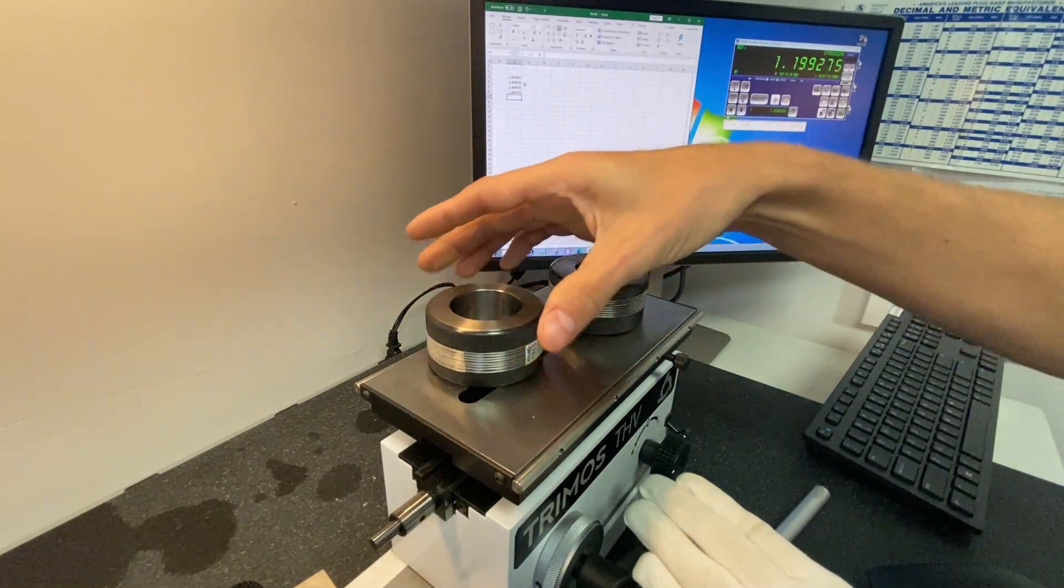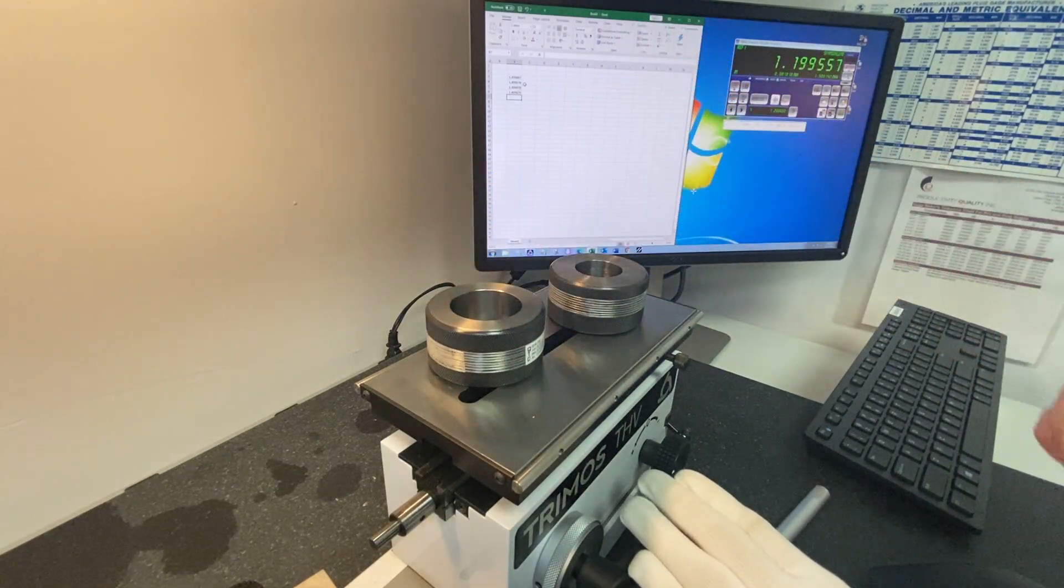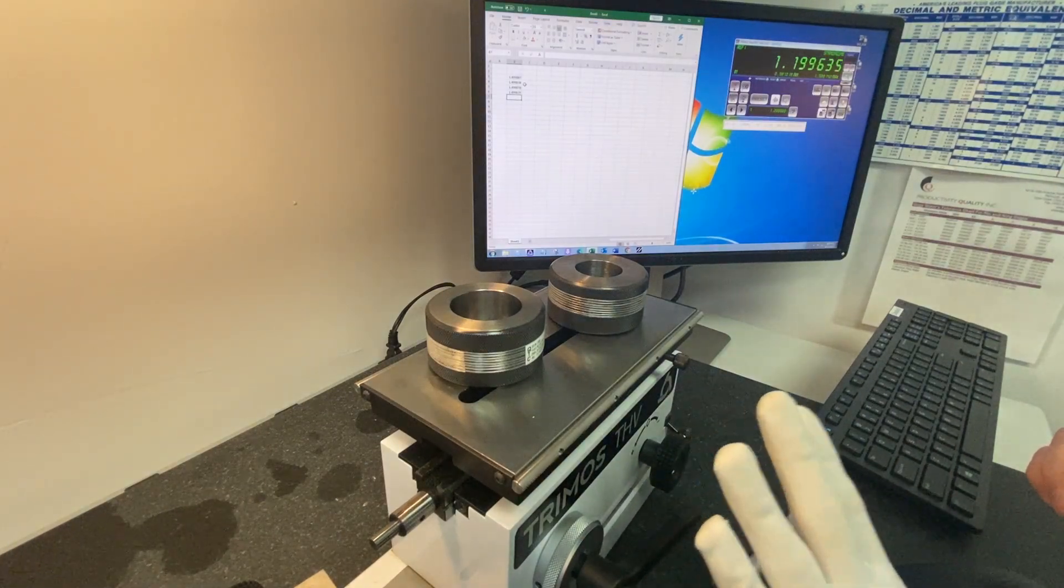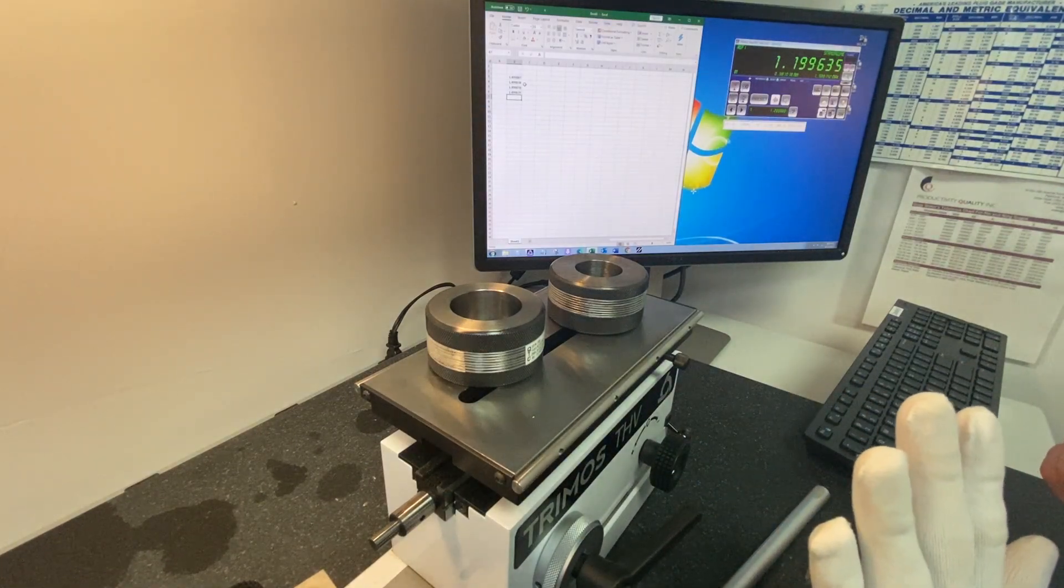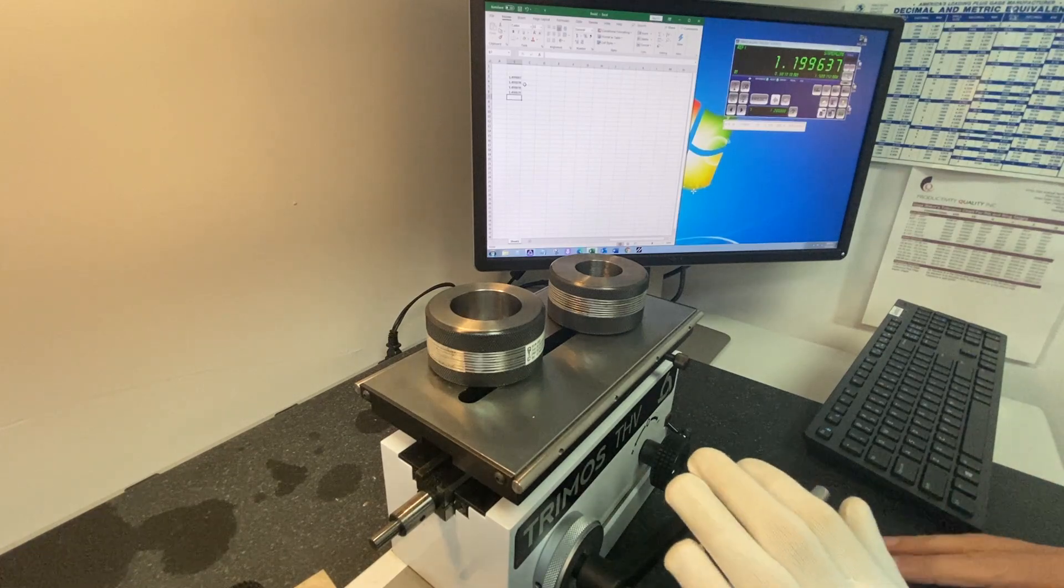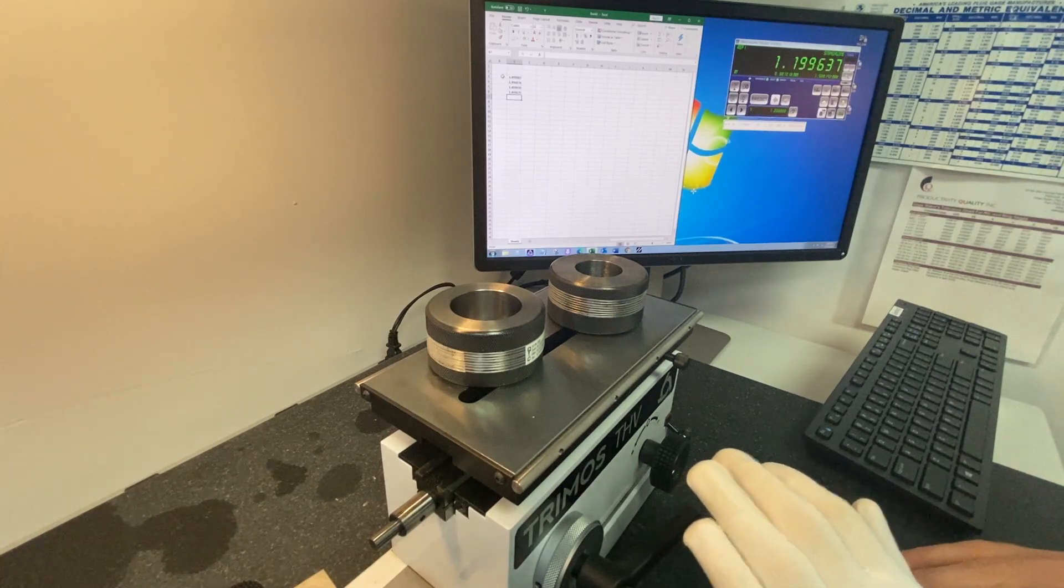And set the gauge again, just as we did before. So that completes the demonstration of the calibration of a ring gauge. I would take all six measurements.